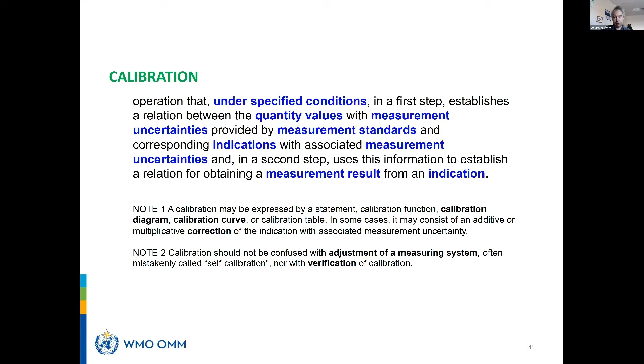Please don't confuse this with the adjustment of the measuring system, nor with the verification. The calibration gives you a calibration curve. A 1-point check is not a calibration, because the instrument must be calibrated all over the range you intend to use it. But the calibration uncertainty is not the measurement uncertainty.